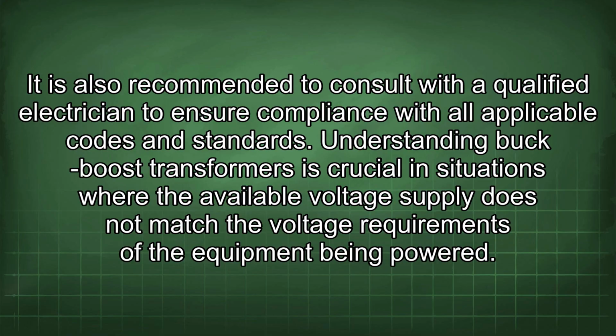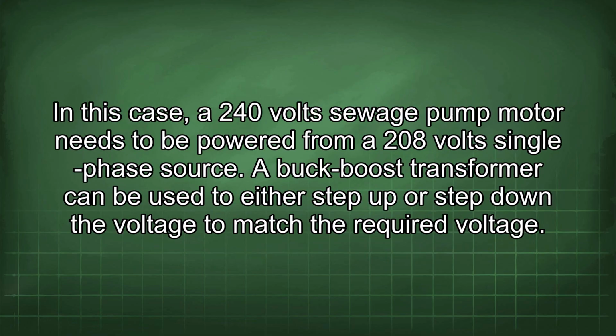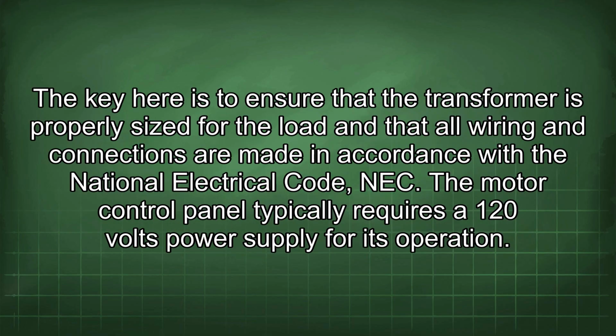Understanding buck-boost transformers is crucial in situations where the available voltage supply does not match the voltage requirements of the equipment being powered. In this case, a 240-volt sewage pump motor needs to be powered from a 208-volt single-phase source. A buck-boost transformer can be used to either step up or step down the voltage to match the required voltage. The key here is to ensure that the transformer is properly sized for the load and that all wiring and connections are made in accordance with the National Electrical Code (NEC).